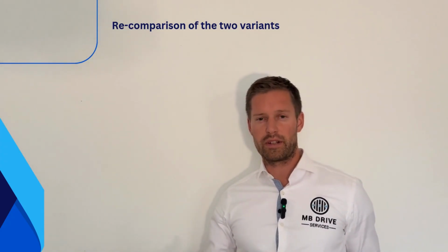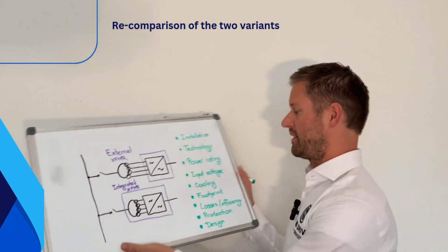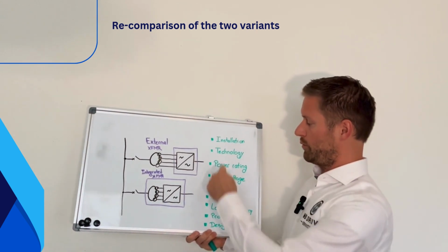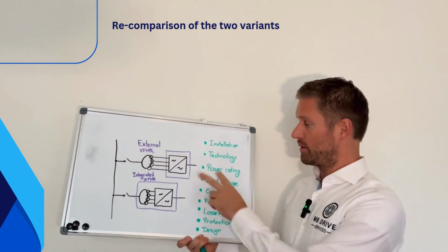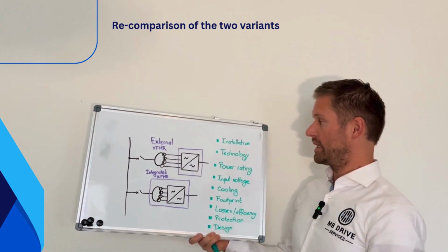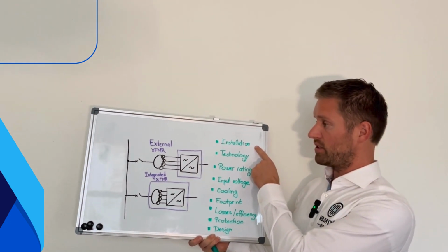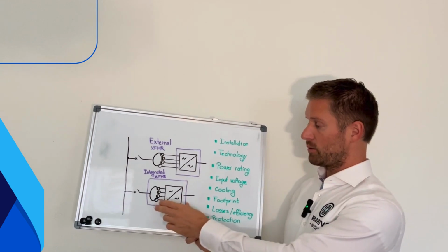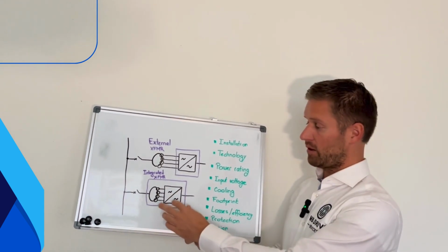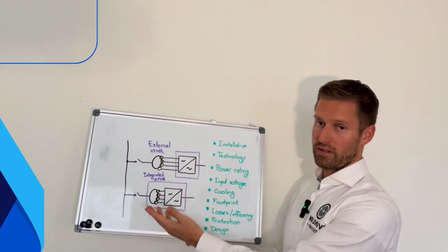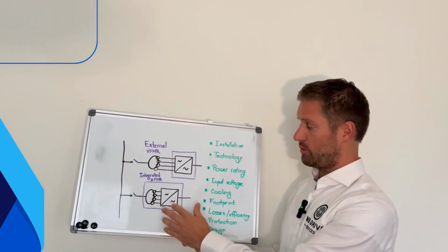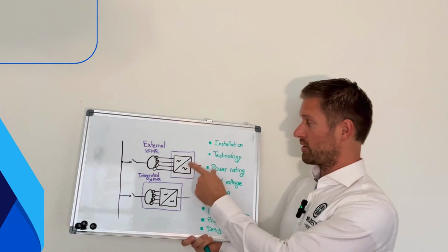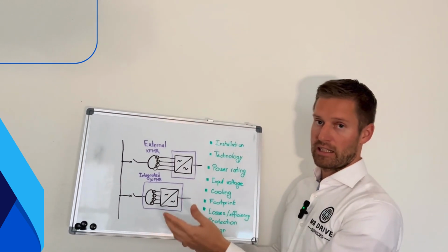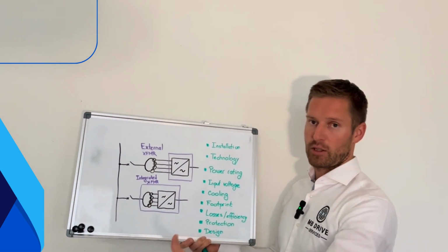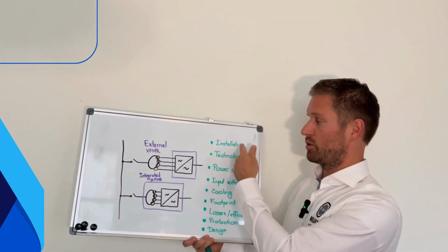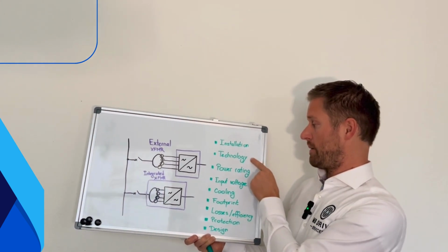So let's come to the comparison of the two variants. I have listed here a few aspects to compare the two solutions. The first point is installation. The integrated transformer, as it's part of the VFD enclosure, is installed indoors in the electric room, obviously in the same room as the VFD. The external transformer can be installed indoors, standing close to the VFD, or outdoors. Outdoors is the typical variant.